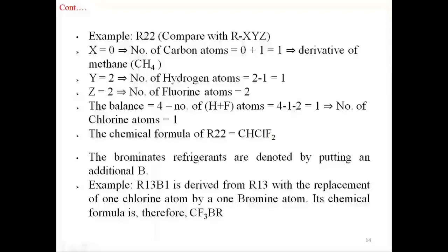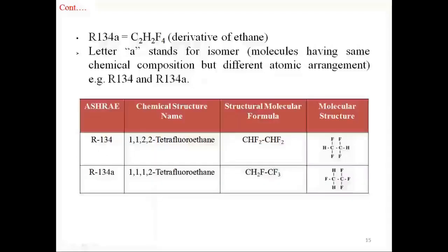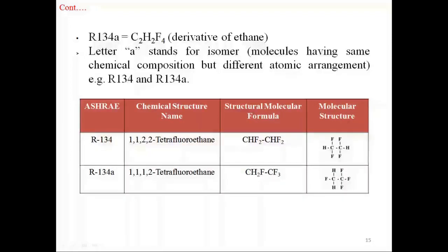Brominated refrigerants are denoted by adding the letter B. For example, R13B1 is derived from R13 with the replacement of one chlorine atom by one bromine atom; its chemical formula is CF₃Br. R134A: the alphabet A is lowercase. The chemical formula is C₂H₂F₄, a derivative of ethane. The letter A stands for isomer — molecules having the same chemical composition but different atomic arrangement. For example, R134 has the chemical structure name 1,1,2,2-tetrafluoroethane, whereas R134A has the structure name 1,1,1,2-tetrafluoroethane.